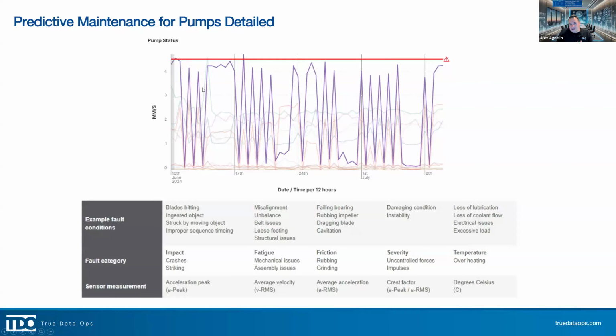What we have here is a pump that, with these sawtooth horns, is telling me it's short cycling. It's on, then off, then on, then off. That's really bad behavior for an electrical component. If this was hooked up to a traditional system without machine learning, based on this red line indicating an ISO standard, I'd get an alert here and here. That's it. But in reality, this device keeps short cycling.